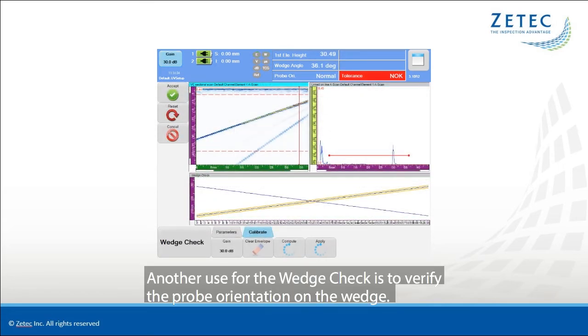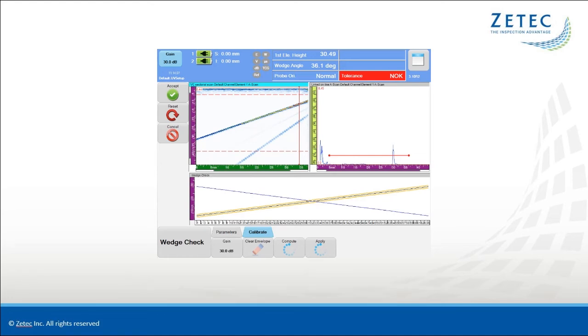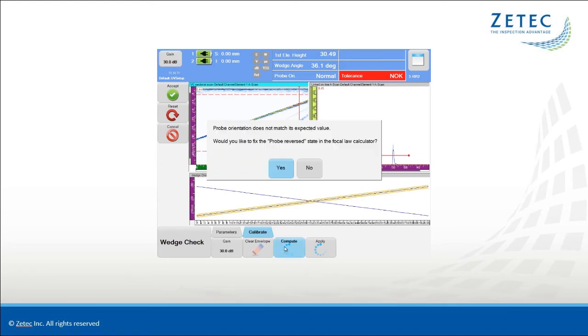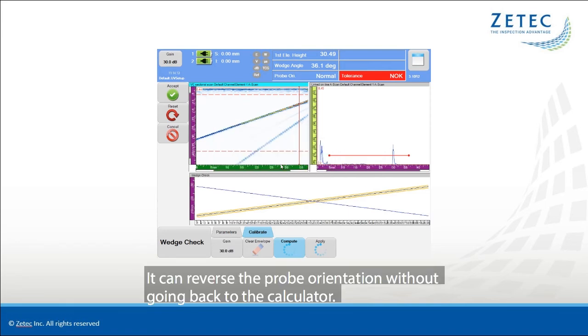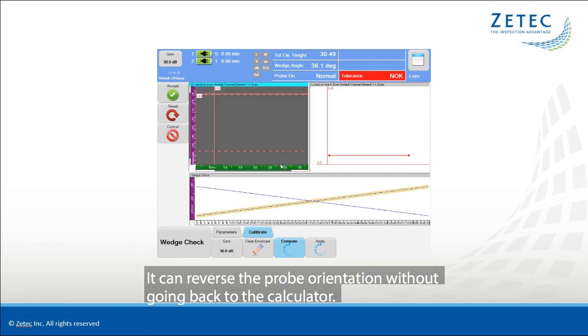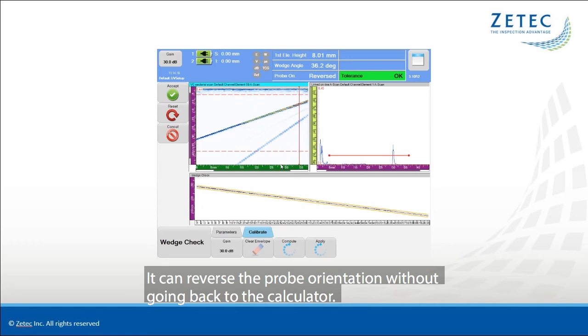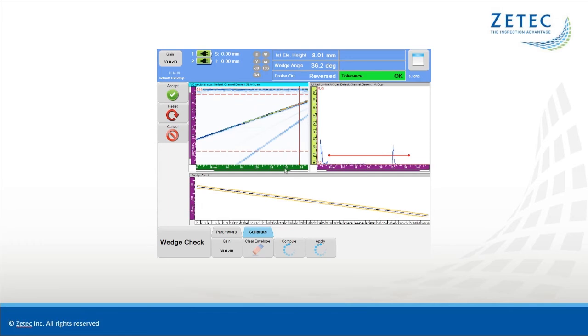Another use for the Wedge Check is to verify the probe orientation on the wedge. It can reverse the probe orientation without going back to the calculator.